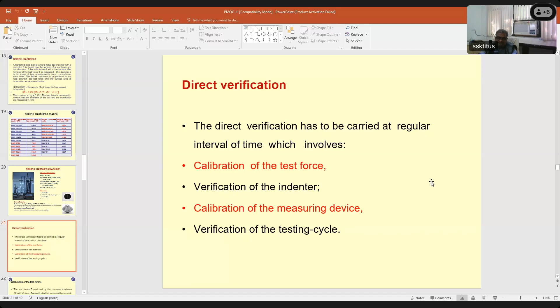The indenter geometry has to be verified, and the calibration of the measuring device, and the verification of the testing cycle. These are the four components involved in establishing the hardness machine and disseminating the hardness scale. Now, how to make it? So, for the testing of the forces, what is the requirement?